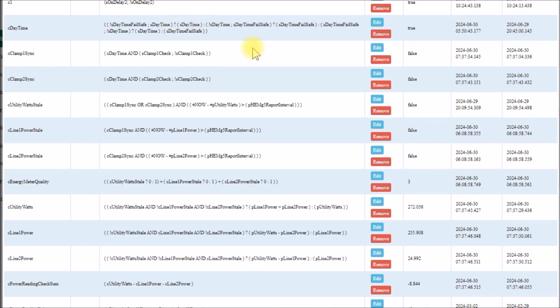I've updated my Notepad++ file to reflect that change. It did take a little bit of time to figure this out. It took me a few days to work out the logic. And with this, you have to get into the event-driven mode because, again, these are events, and these sequence operators depend on the time that these schedules went true or false, not the current state. It's what time did the last change happen.